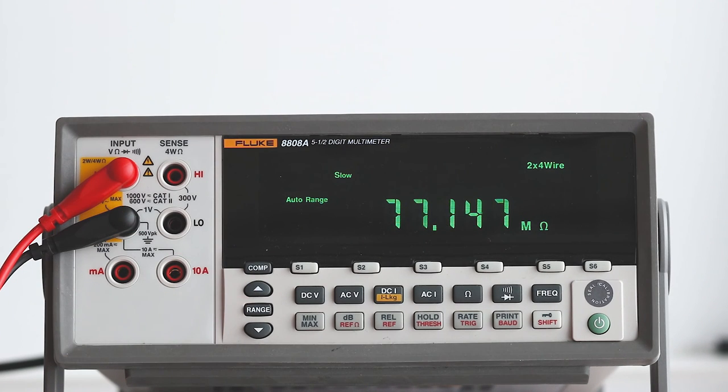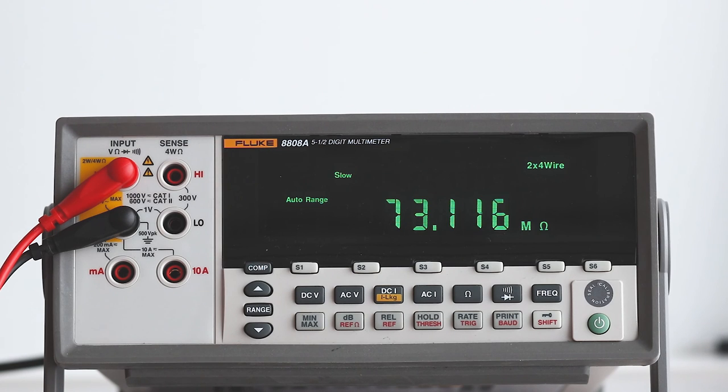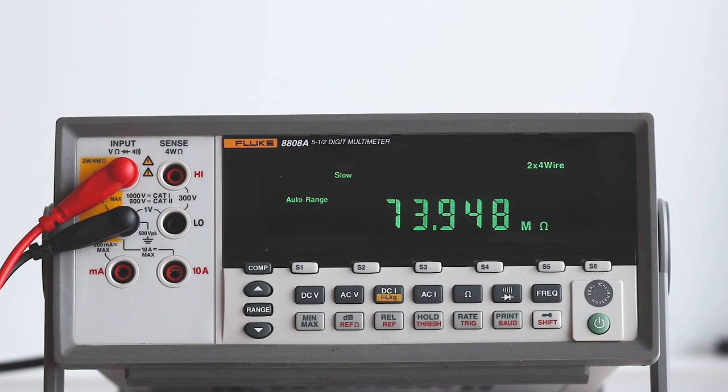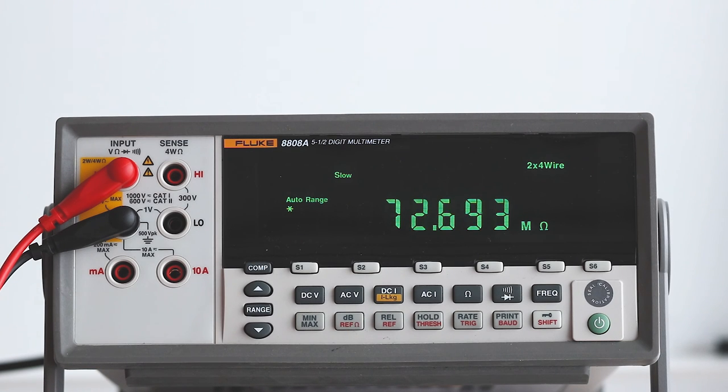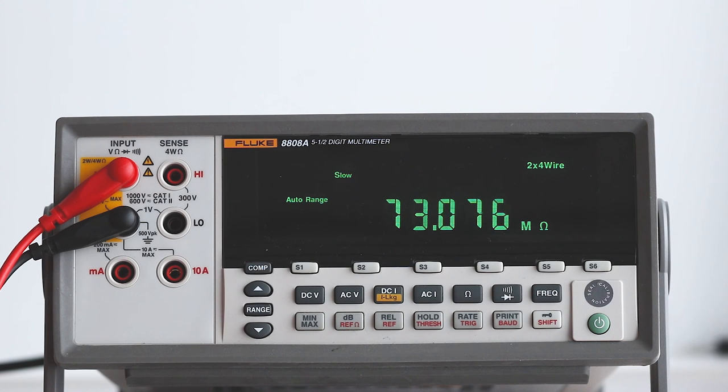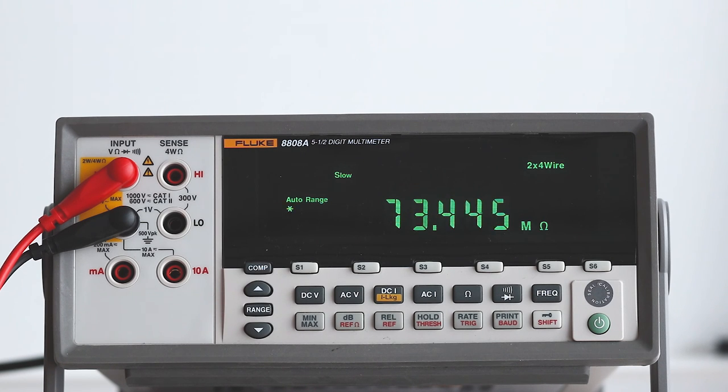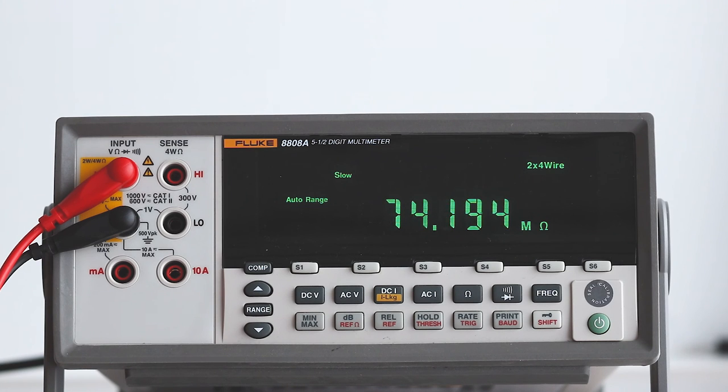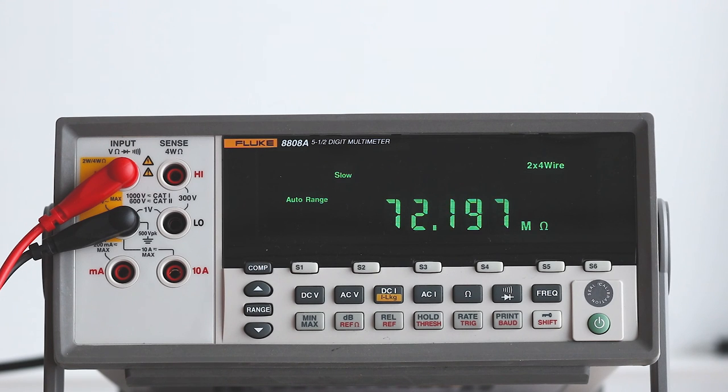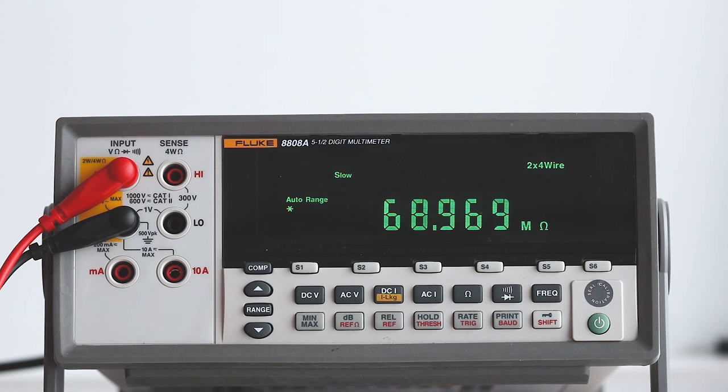A clamp-on device measures the magnetic field surrounding a conductor, and there is no direct electrical connection. Very low current resistance measurements are notoriously difficult to make where a high level of precision is required. The Fluke 8808 multimeter offers a unique solution that is not seen in hand-held multimeters. It is the 4-wire resistance measurement. To see how it works, first we'll touch the probes together using the conventional 2-wire resistance hookup.